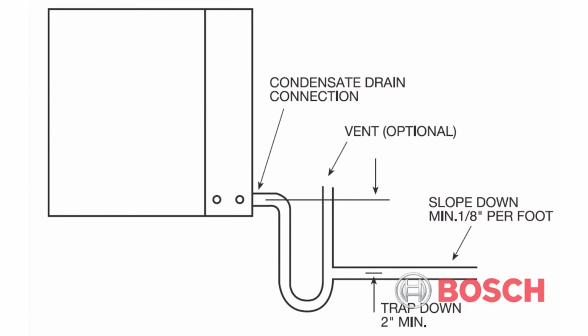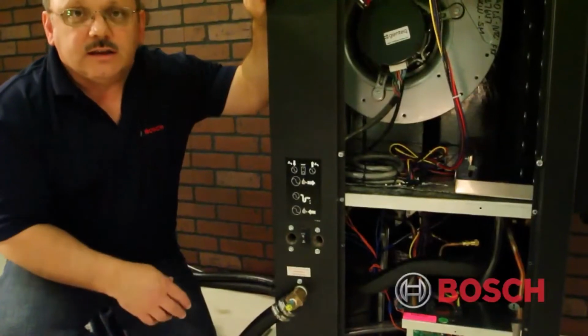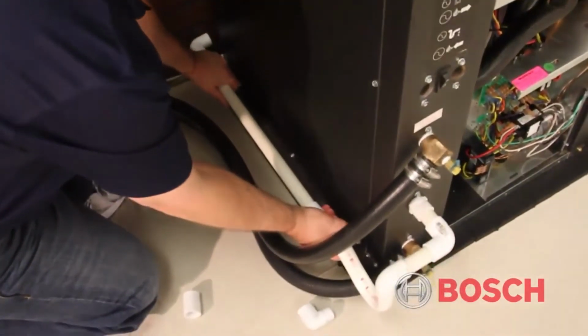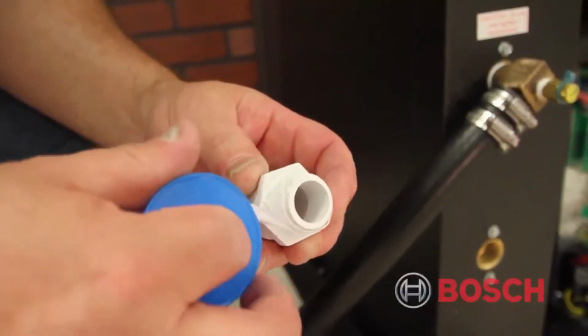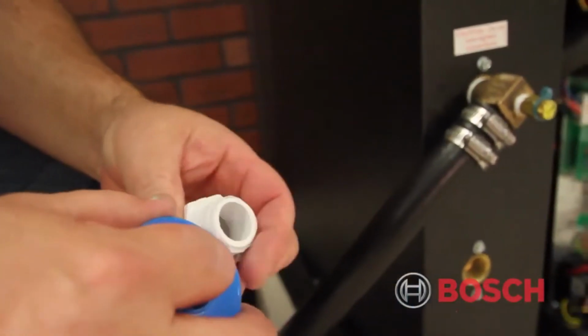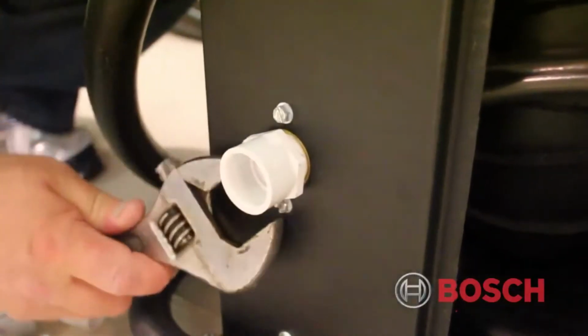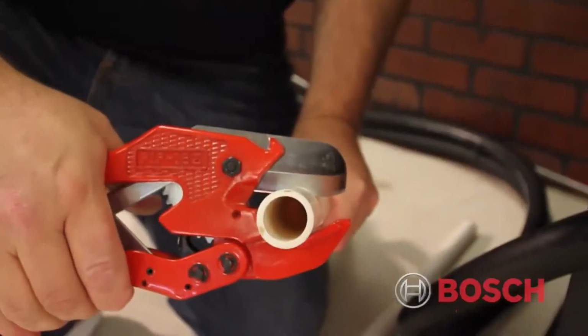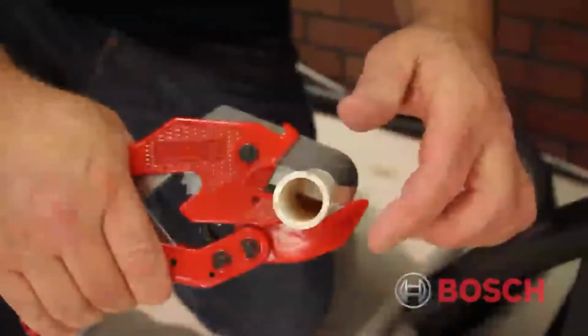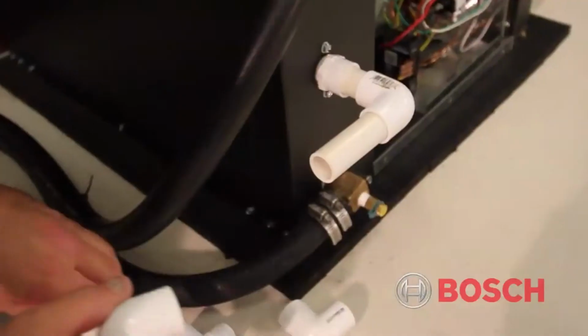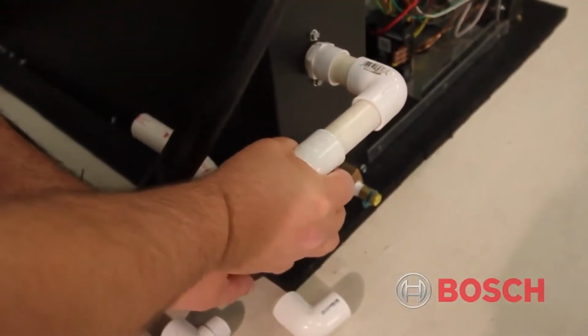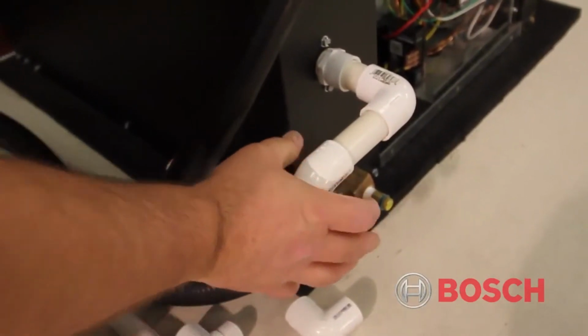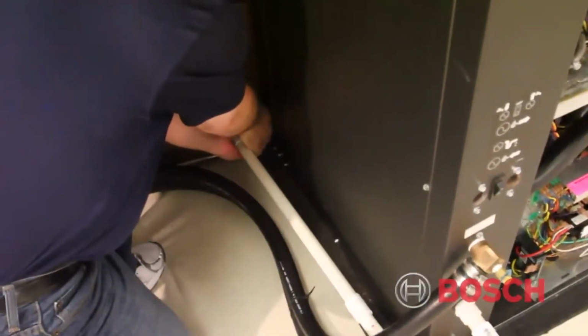There may be some additional requirements for condensate trapping in your area, such as clean out tees and vents and those types of things. It's always a good idea to dry fit everything before you glue it together. So the first thing we'll do is apply some Teflon tape to our male adapter. We'll take the male adapter and thread it into our female fitting that is attached to the front of the unit right between your two water loop connections. Once we have that tightened down, we will cut a couple short pieces of PVC, attach our trap to the male adapter on the front of the unit, and then we'll take a 90 out behind the unit to connect to our existing drain line.